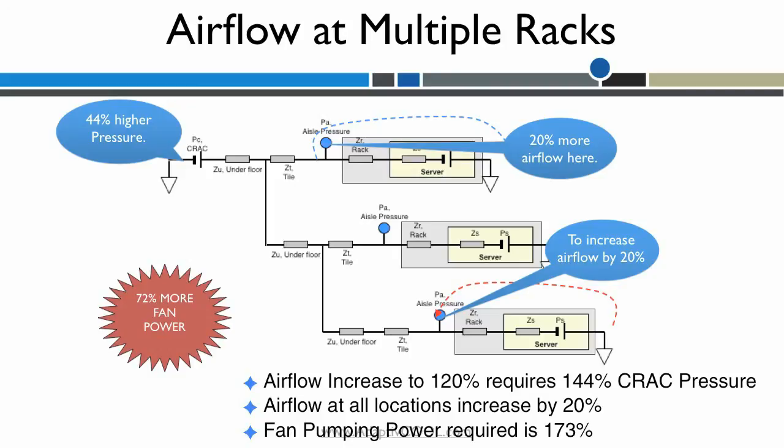This is primarily because of the underfloor impedance and limitations due to the fan loss. To conclude, controlling air flow distribution in a data center to match heat distribution in the room is the primary source of cooling efficiency. The pattern and level of underfloor obstructions make it difficult to achieve the right air flow distribution without some active approach such as demand based cooling.